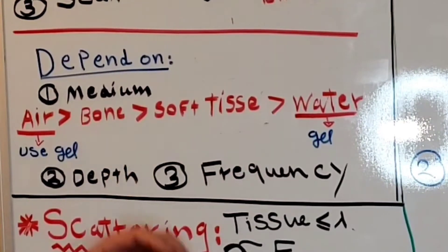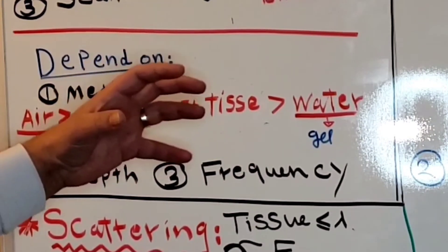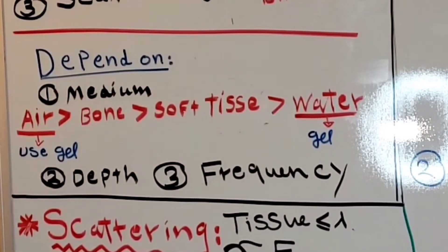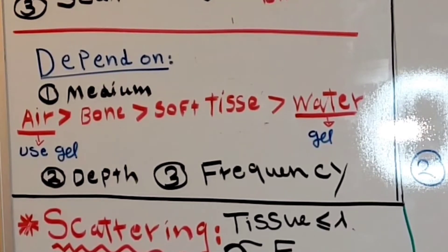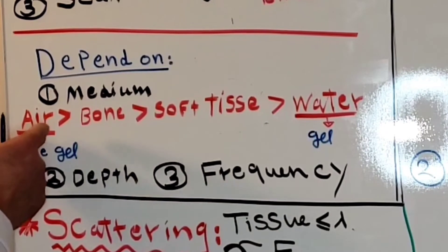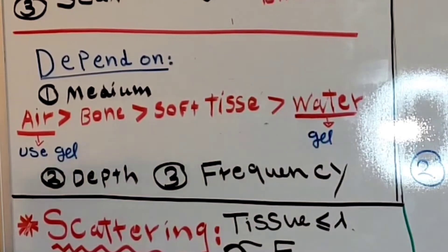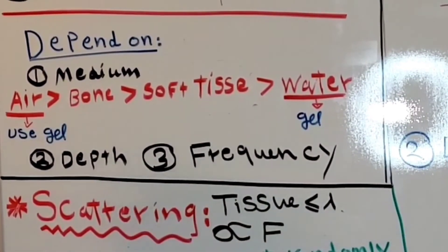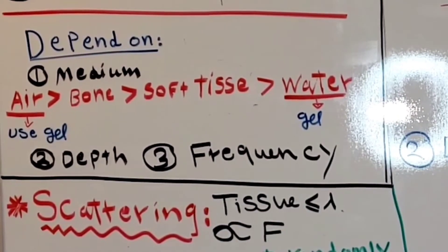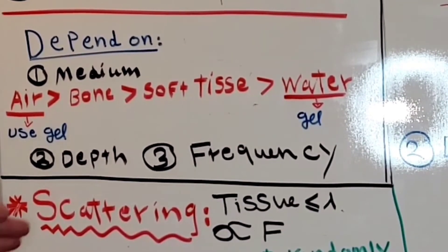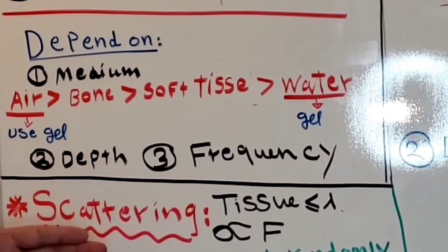We can use a full urinary bladder as an acoustic window to look at the uterus. Also, because air has high attenuation, we use gel to fill the gap between the transducer and the skin. We also use gel because it has an acoustic impedance that matches between the transducer's matching layer and the skin.